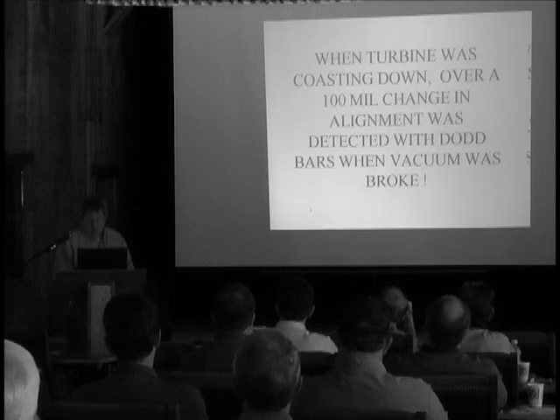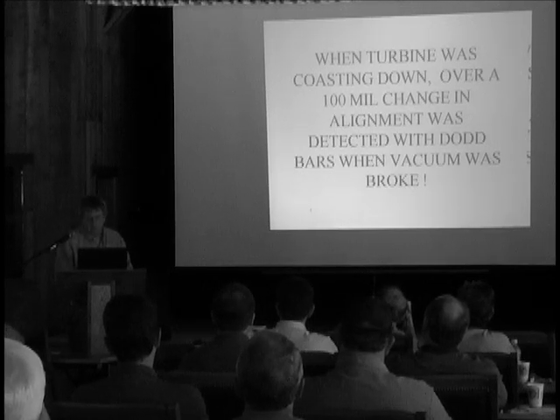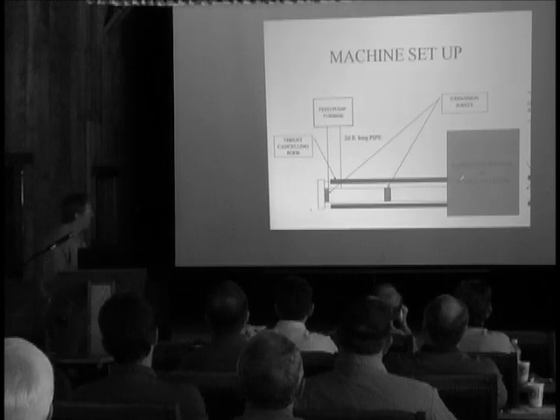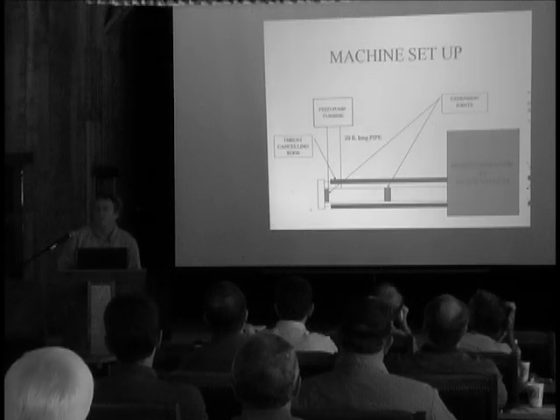So I looked at the foundation of the turbine, and I noted there were even cracks in the foundation. We're going to get back to our friend here I talked about before. So you go down below, and this is the arrangement. You have your main condenser. It's running at about 14.5 psi vacuum. In other words, it's about as close as you're going to get on your vacuum.